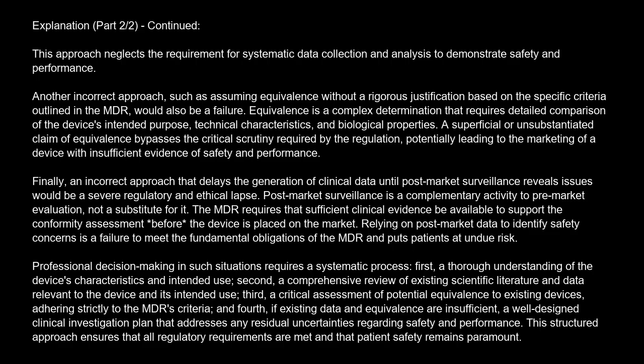Another incorrect approach, such as assuming equivalence without a rigorous justification based on the specific criteria outlined in the MDR, would also be a failure. Equivalence is a complex determination that requires detailed comparison of the device's intended purpose, technical characteristics, and biological properties. A superficial or unsubstantiated claim of equivalence bypasses the critical scrutiny required by the regulation, potentially leading to the marketing of a device with insufficient evidence of safety and performance.